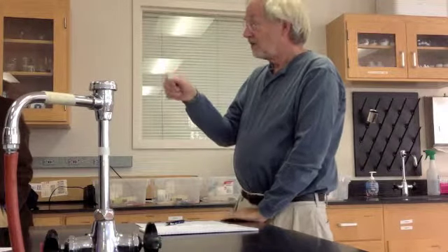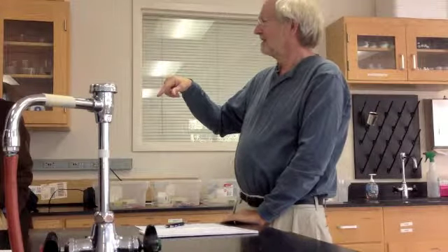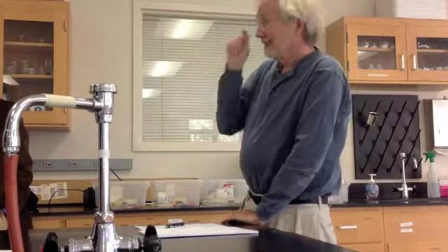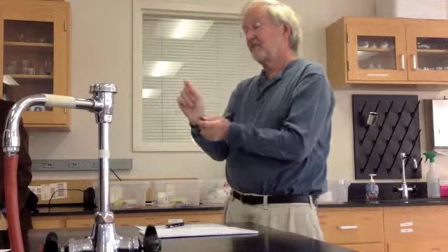If you go to the hospital and look at how they control the valves, go to the valve, turn it all the way off. There's a little meter above it that says how many liters a minute. They still have those, don't they? Oh, yeah. See how many turns you have to make before it goes from the bottom to the top reading. And then calibrate it. Like how many turns per liter? So then you find the diameter of it at the end. Yeah, then you find the diameter at the end, and that's what you need to look for, is to open the valve up and see what that opening is, to see what size you need.